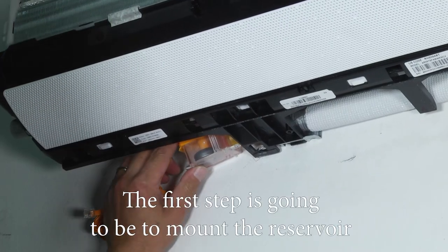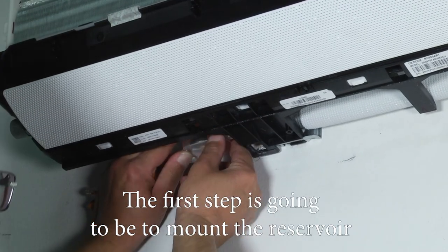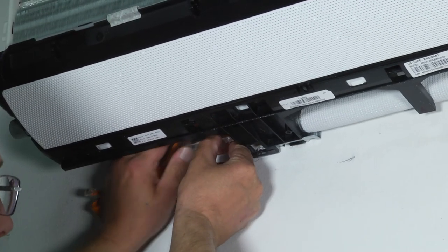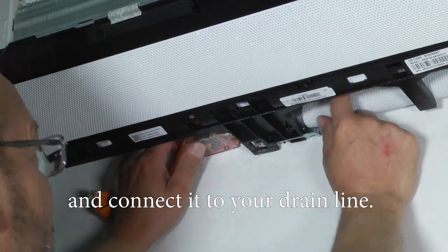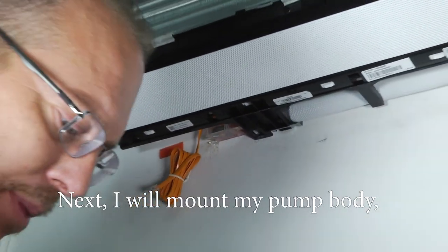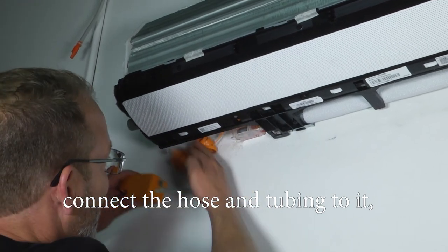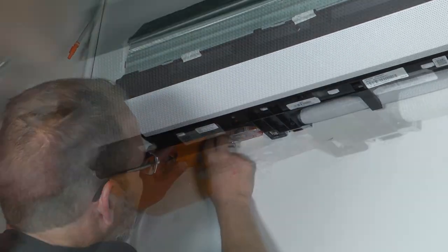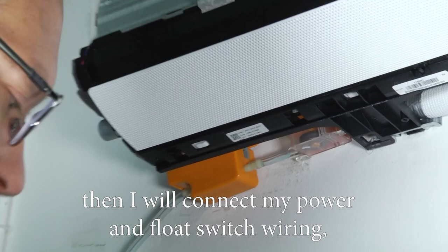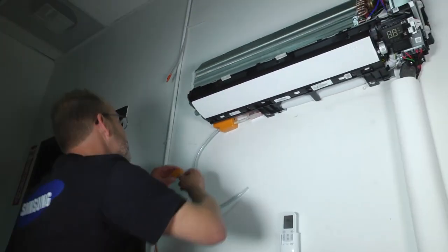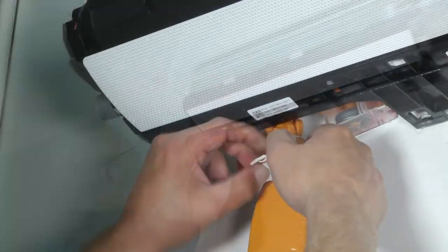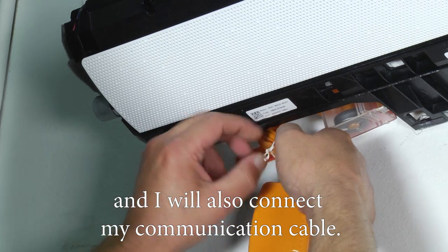The first step is going to be to mount the reservoir and connect it to your drain line. Next I'll mount my pump body, connect the hosing tubing to it, then I'll connect my power and float switch wiring, and I'll also connect my communication cable.